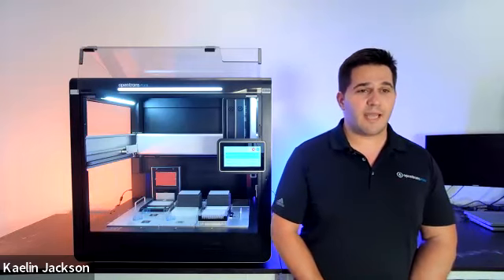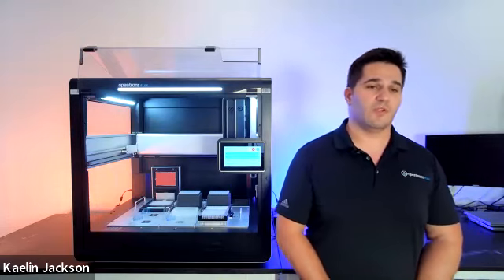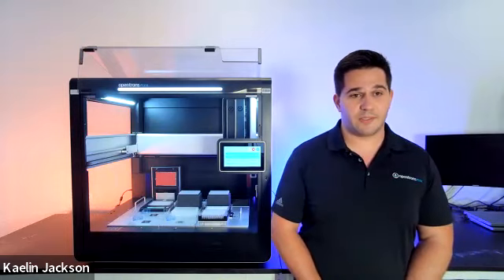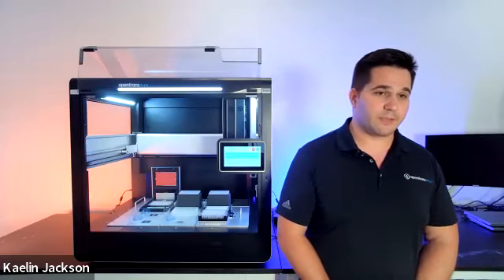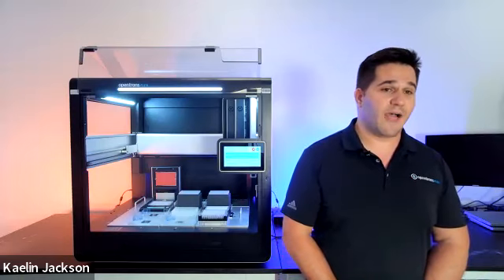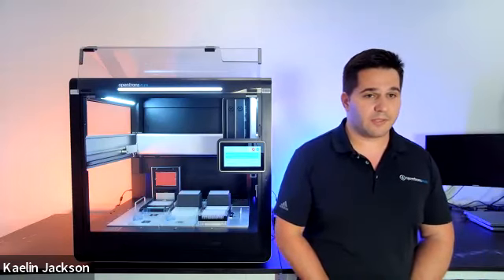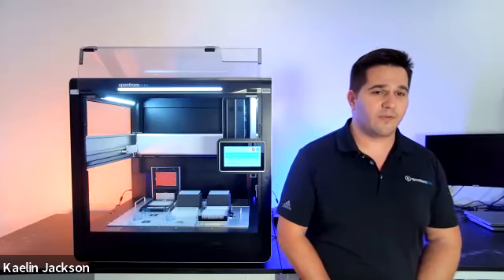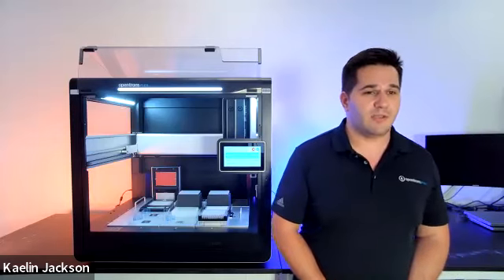The pipettes available are single channel, 8 channel, and 96 channel. The single channel and 8 channel come in 2 sizes. The P50, which covers 1 microliter to 50 microliters, and P1000, which covers 5 to 1000 microliters. The 96 channel comes in only 1 size, which covers 5 microliters to 1000 microliters. These are really wide volume ranges that offer a lot of flexibility for a lot of applications that require different volumes. One that comes to mind is nucleic acid extraction.